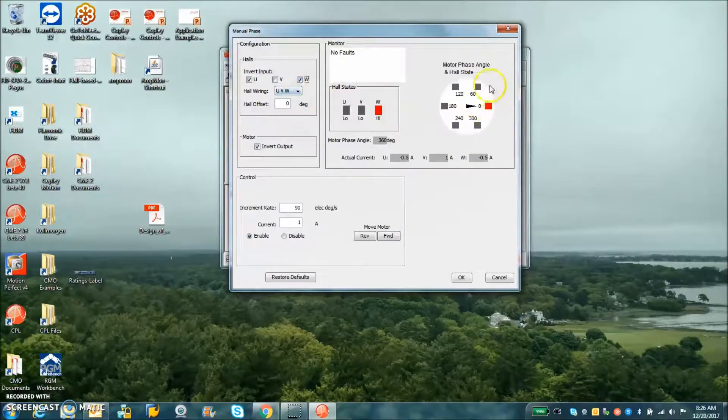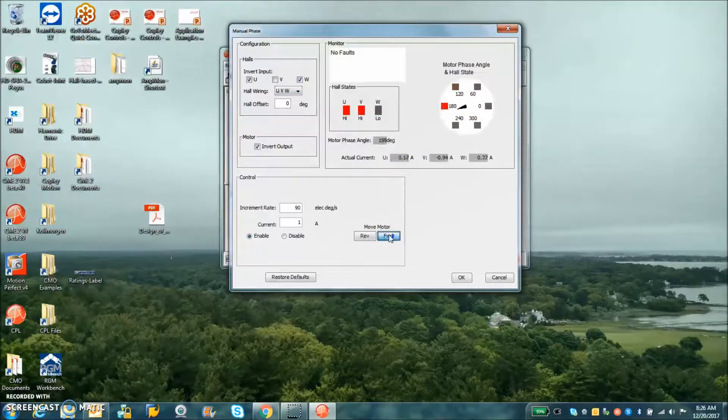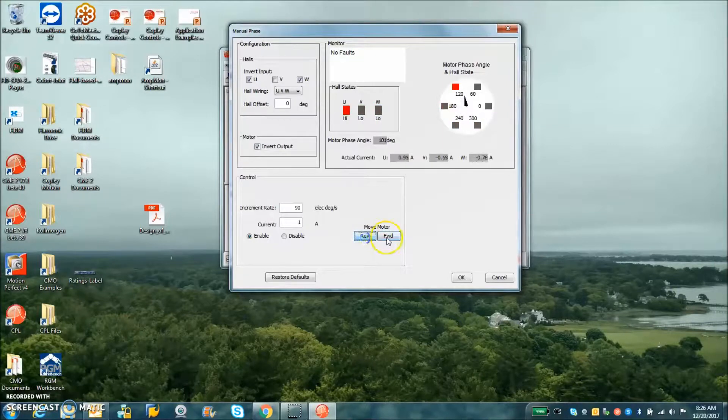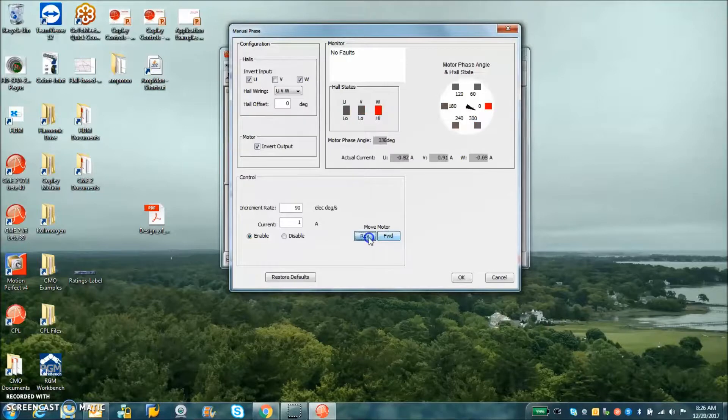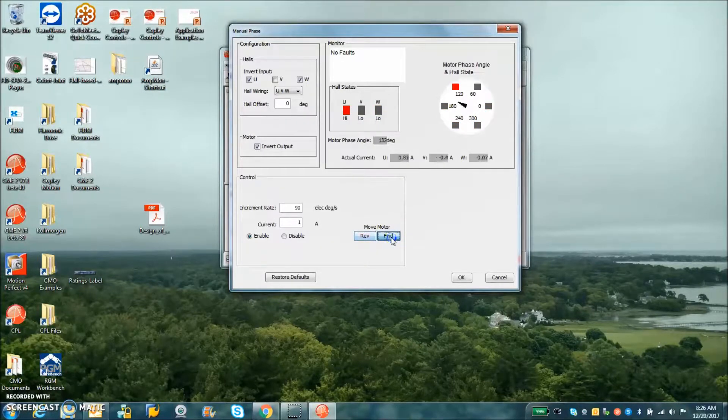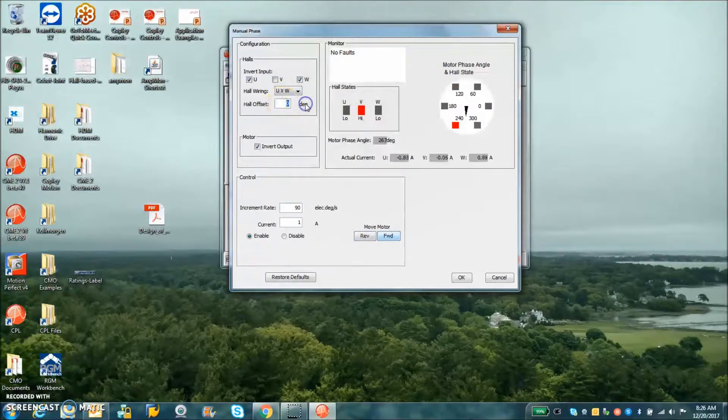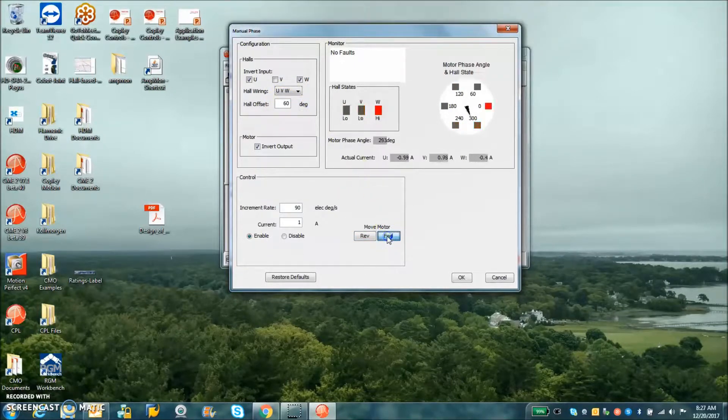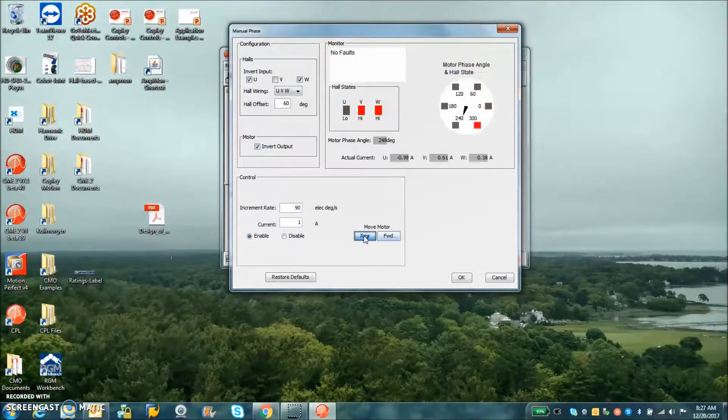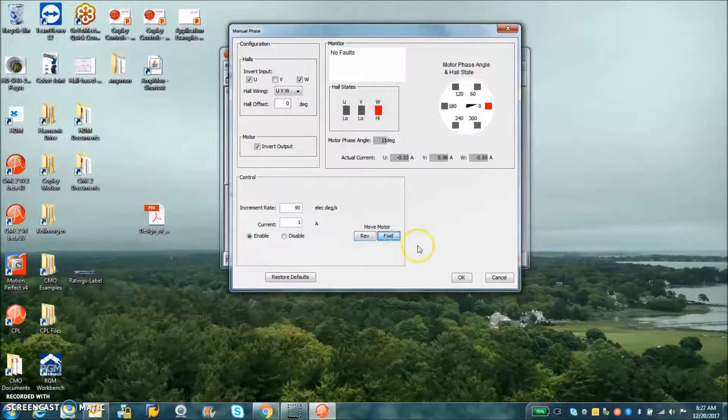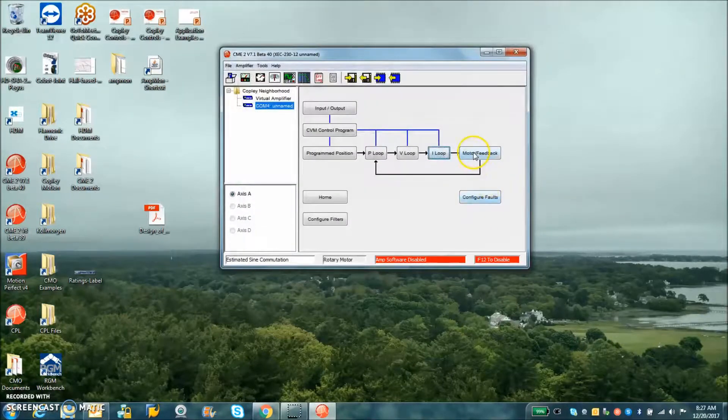If you remove the cabling the hall state will go away. The idea is that the red indicator should be balanced whether you go forward or reverse with respect to the black needle. If it's not, you can adjust the hall offset to affect the lead and lag of the phase.